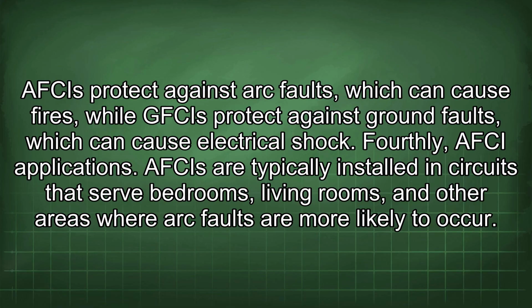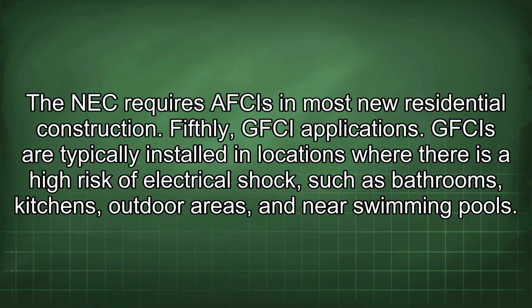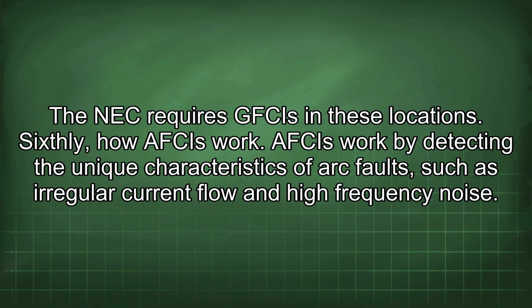Fourthly, AFCI applications. AFCIs are typically installed in circuits that serve bedrooms, living rooms, and other areas where arc faults are more likely to occur. The NEC requires AFCIs in most new residential construction. Fifthly, GFCI applications. GFCIs are typically installed in locations where there is a high risk of electrical shock, such as bathrooms, kitchens, outdoor areas, and near swimming pools. The NEC requires GFCIs in these locations.